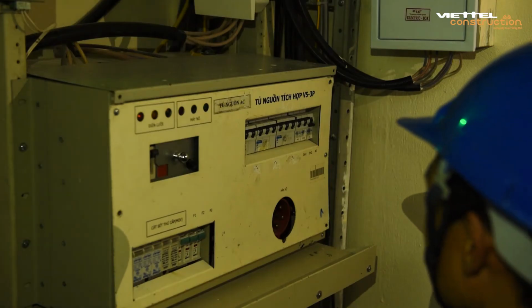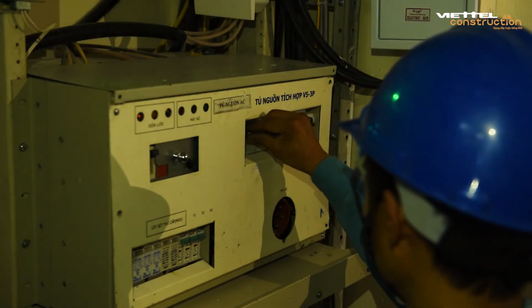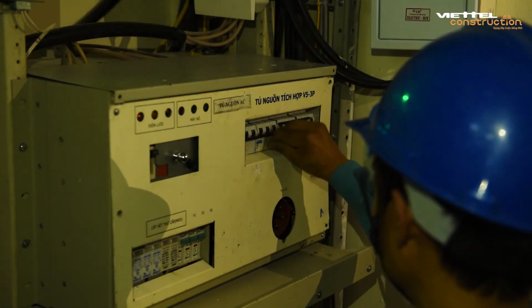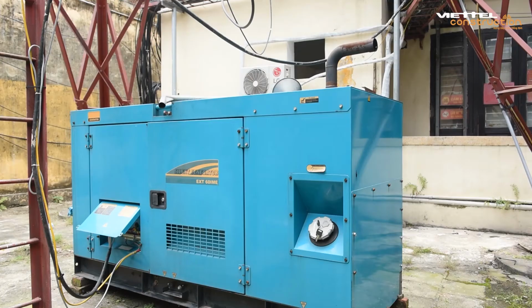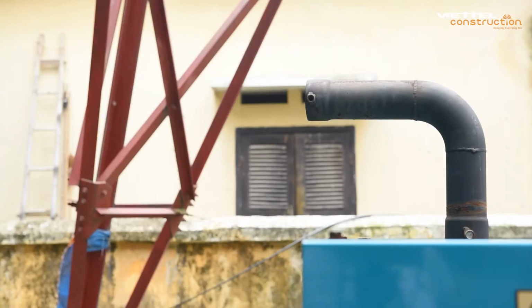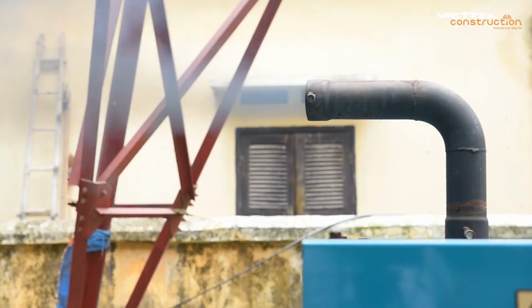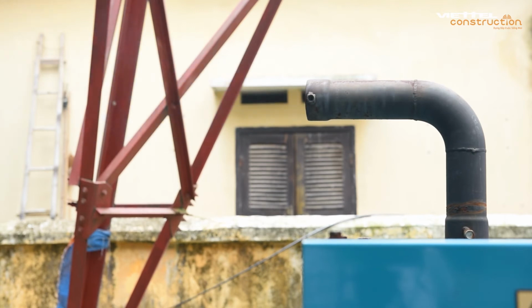Decrease the battery charge or capacity until the station capacity is met, but not exceeding a maximum of 50% battery capacity. If still not enough, continue to turn off equipment in the station such as the air conditioner and lights. If there is still not enough operating capacity, the generator must be replaced.